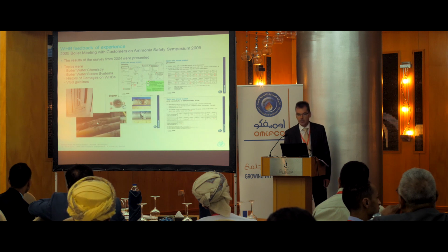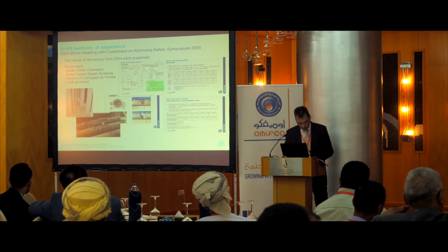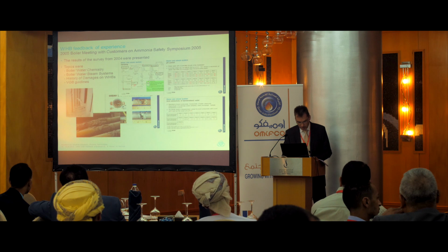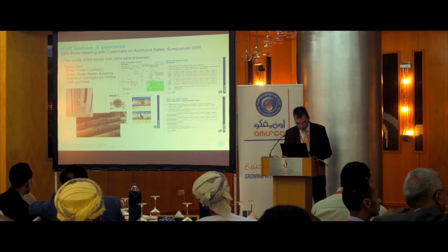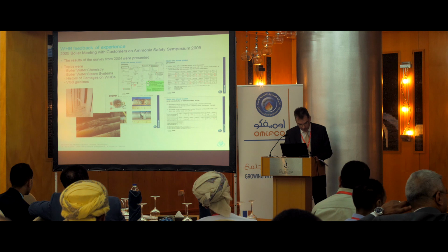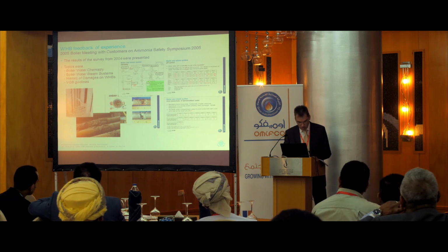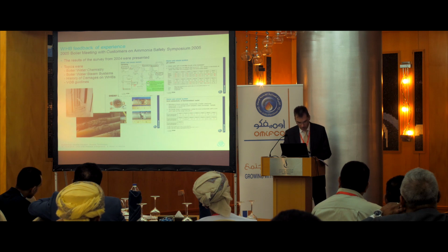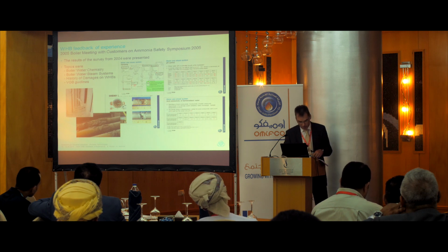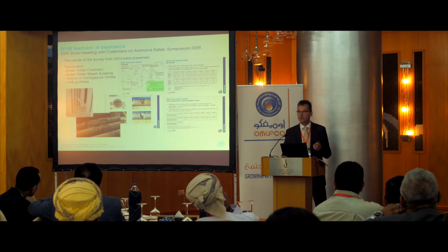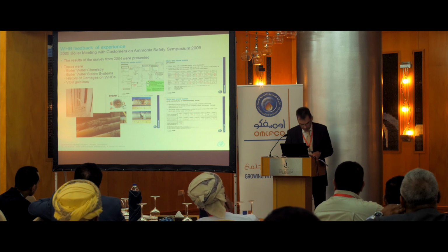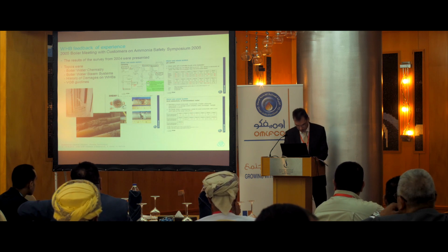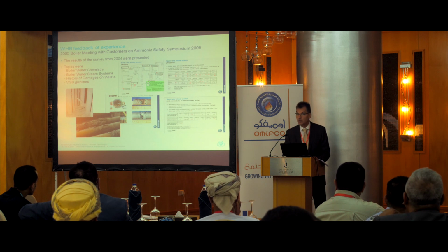And what are the failures? Leaks. Also at the symposium, a paper was presented by recognized specialists from DSM about damages on boilers, pointing out that concentration factors by evaporation, as well as corrosion mechanisms like first condensate corrosion or flow accelerated corrosion, can lead to damages in boilers. The paper came to a clear conclusion: keep your boiler clean and you will not suffer damage. Easily said, but the devil lies in the details. Because what is the problem with the boiler feed water?